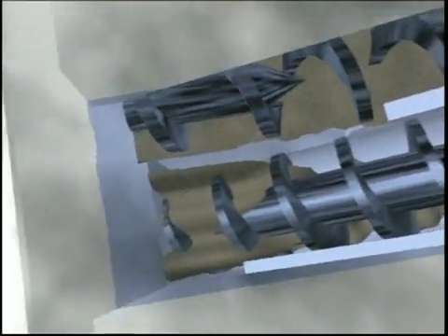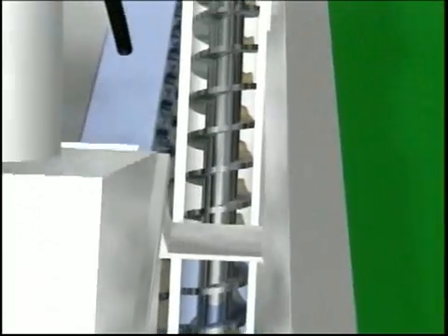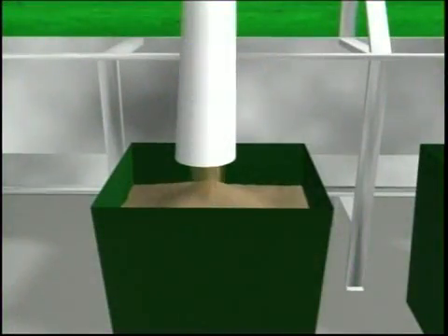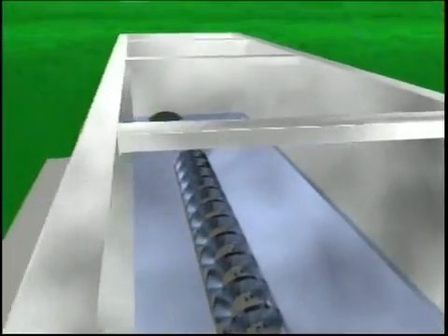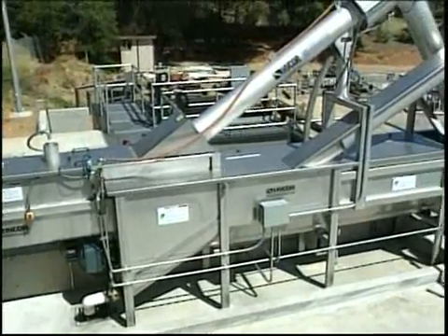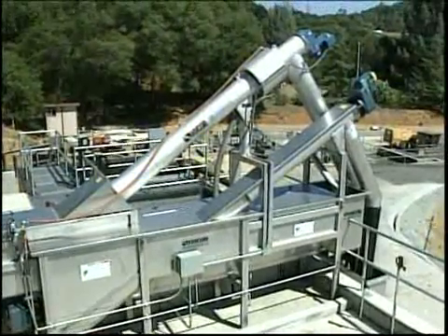The spiral periodically rotates and moves the grit toward the integral classifier. In the classifier, the grit is elevated out of the water. The spiral turns slowly and intermittently, allowing the grit to drain before being discharged. The screened and de-gritted liquid flows over an adjustable weir and onto the rest of the plant for further treatment. Since the entire system is enclosed, it creates less odors. It is safe to operate and easy to maintain.